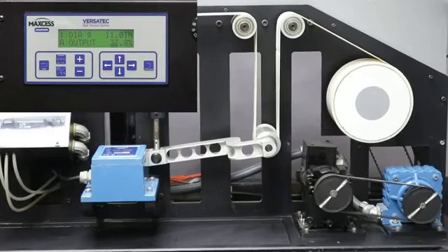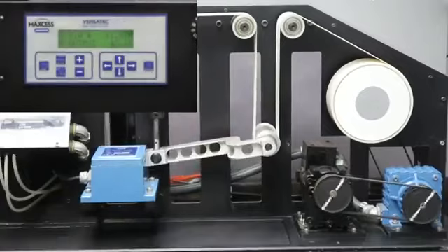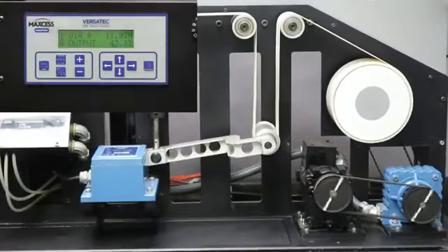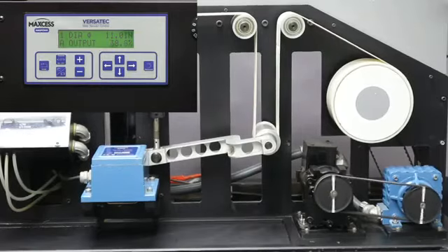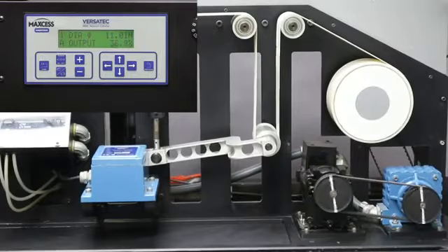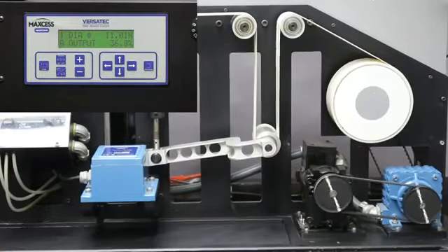Now, when you first turn the machine on, just because it looks stable does not mean that it's tuned. A properly tuned system, and when I talk about tuning, it's tuning the PID parameters, needs to be right on the edge of being unstable, because we need to be able to react to any transients that might come along. If we don't do that, even though it looks stable, it might just be sluggish right now, and we'd end up bouncing off of the top or the bottom stop.